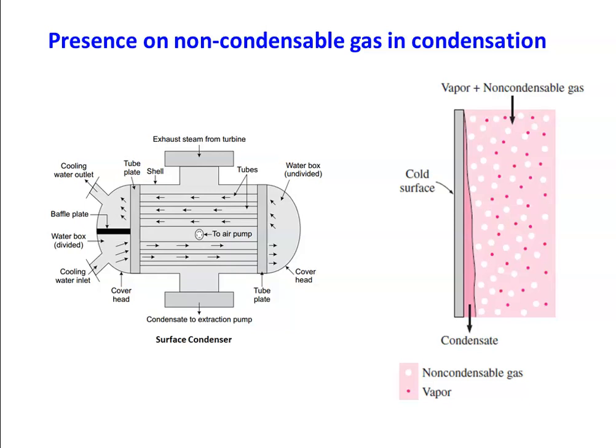Because the condenser operates at vacuum pressure, and there are mechanical joints throughout the condenser, air can leak in from the outside. This leaked air must be removed to maintain the low pressure, which is why an air pump is connected to the condenser. Periodically, using the pump, air is removed from the condenser.